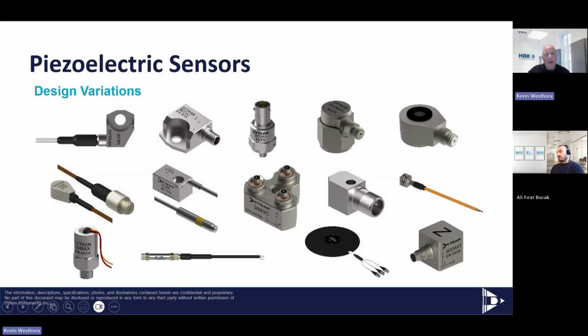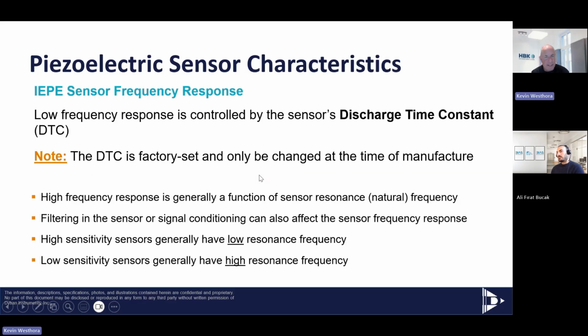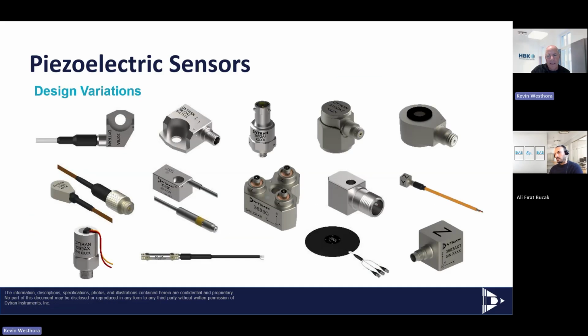All right, the next thing I want to talk about is frequency response, the low-end frequency and the upper high-end frequency. Let's first start with the upper frequency. Let's go back to this picture here. It's kind of hard to tell, but this sensor right here, I don't know if you can see my cursor in the middle on the right, is a fairly large accelerometer. This is an industrial accelerometer meant to monitor rotating pieces of equipment like pumps, motors, things like that. The connector is very, very robust compared to like the 10-32 connector above it. So it's an industrial accelerometer.